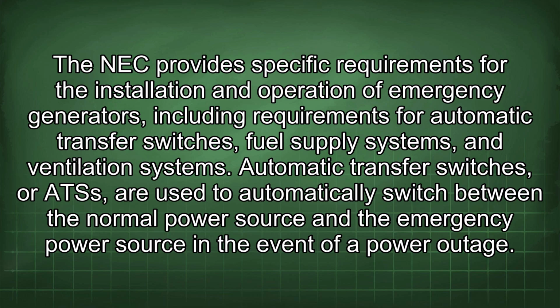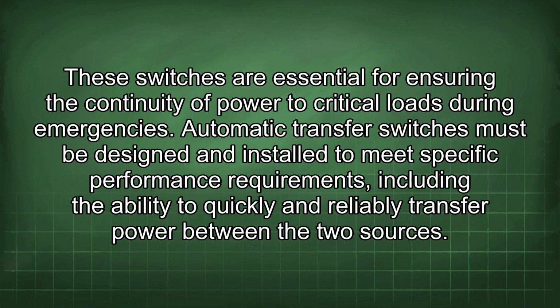Automatic transfer switches, or ATSs, are used to automatically switch between the normal power source and the emergency power source in the event of a power outage. These switches are essential for ensuring the continuity of power to critical loads during emergencies. Automatic transfer switches must be designed and installed to meet specific performance requirements, including the ability to quickly and reliably transfer power between the two sources.